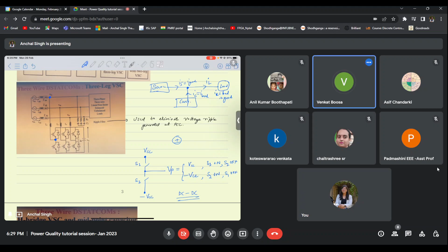Yes. Compensation. So now what happens is, I know that I need to make a current controlled compensator that will supply the bad part of the current. So when I am talking about current control, this is the compensator current of phase A. That means I have to control ICA in such a way that it supplies the bad part of the load. Now, here this is a voltage source converter, right? That means it has control over voltage. So at this point A, I am controlling the voltage so that the current in this branch can be changed.